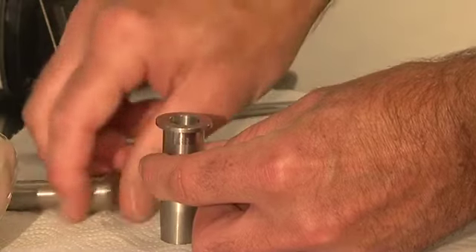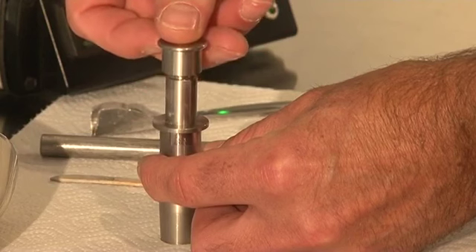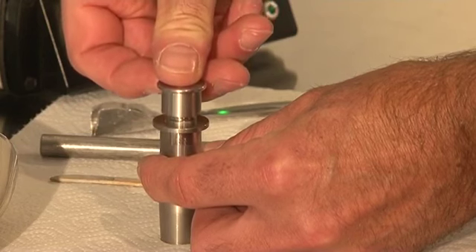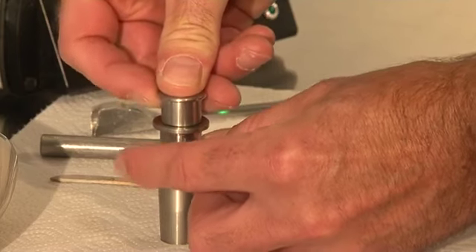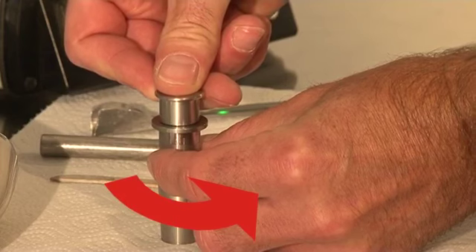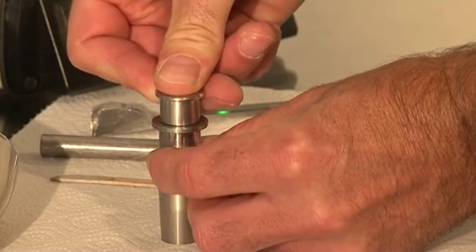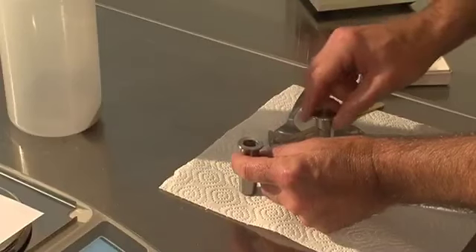Carefully press the plunger onto the powder bed until the underside of the collar touches the cap of the cell. Slowly withdraw the plunger, approximately 5 mm, rotate it through 90 degrees and press it onto the powder bed again. Slowly withdraw the plunger from the compacted powder bed without disturbing it.